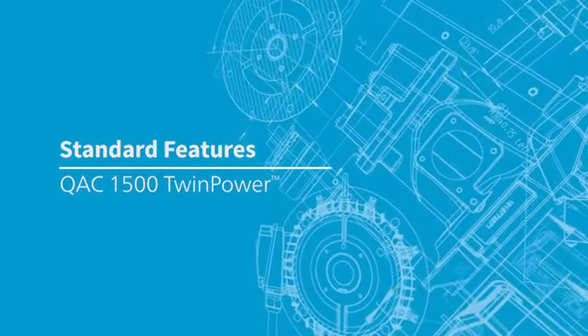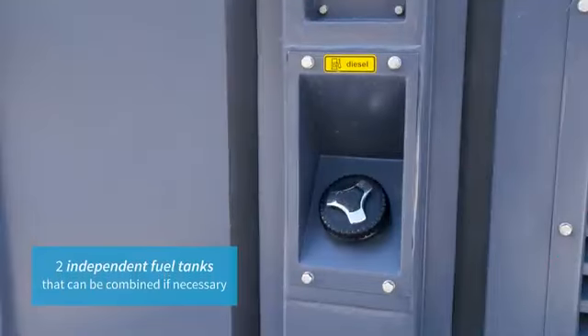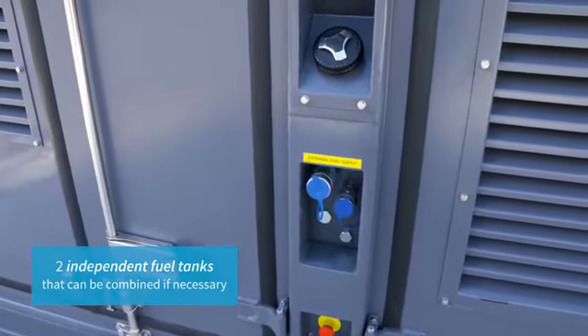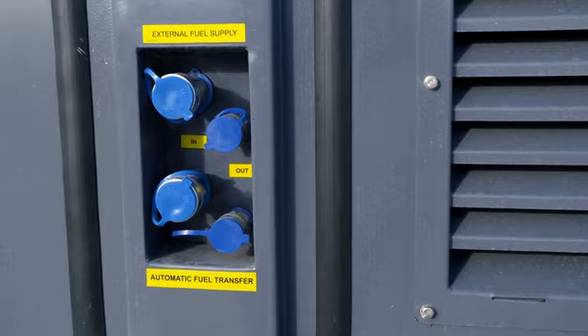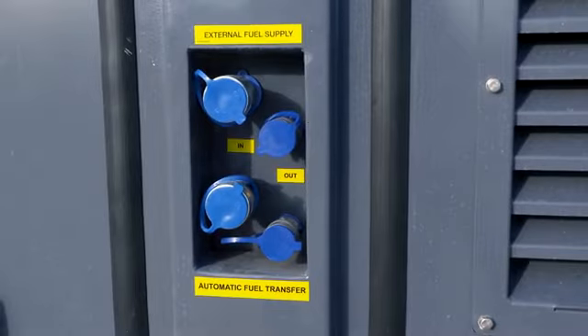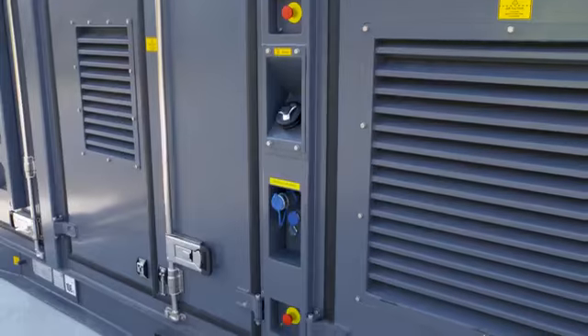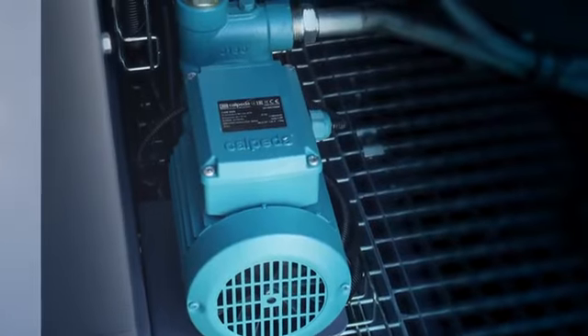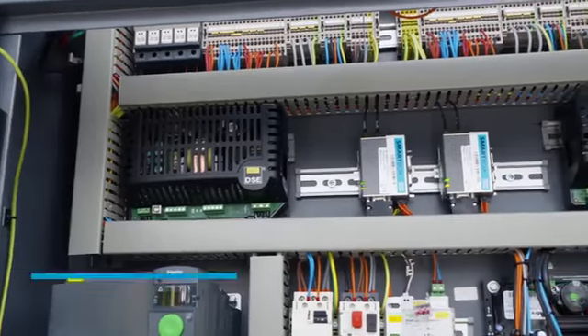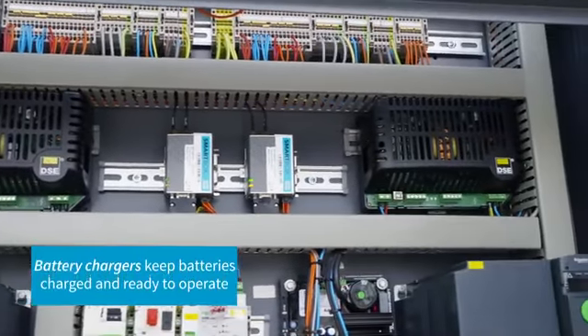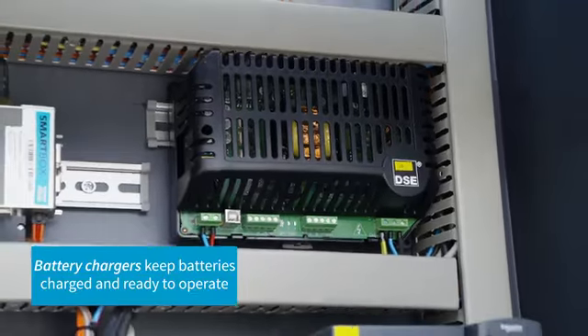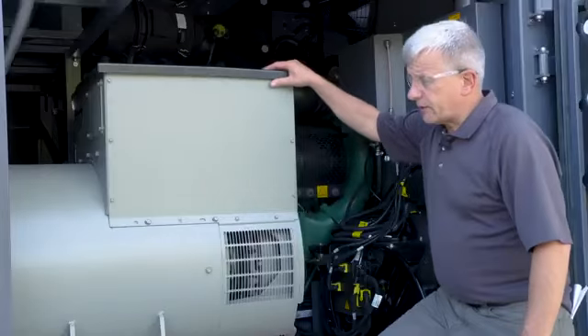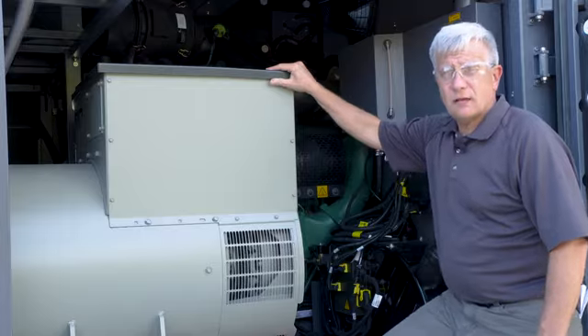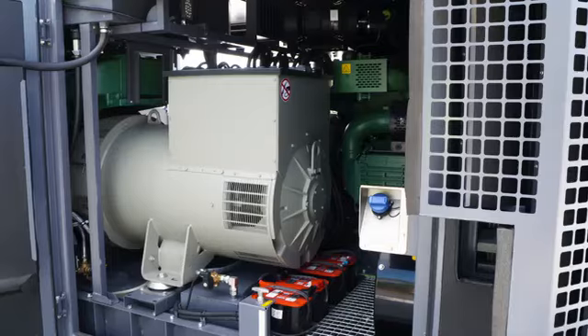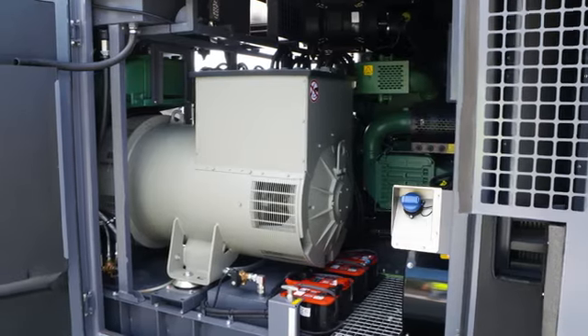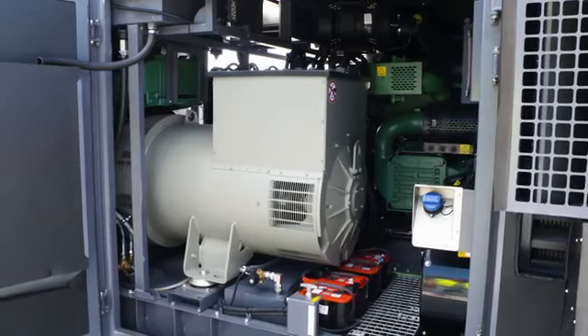Standard features. There are 2 independent fuel tanks, one for each engine, that can be combined if necessary. You can easily increase fuel autonomy by connecting a fuel cell to the external fuel connections or by refilling the internal tanks using the auxiliary fuel pump included in each container. Another feature are the battery chargers that will keep the batteries properly charged and ready to operate even after long periods of inactivity. Inside the container, we have a 725 kVA alternator with the anti-condensation heaters installed, intended to keep the alternators warm enough to avoid water condensation in high humidity environments.